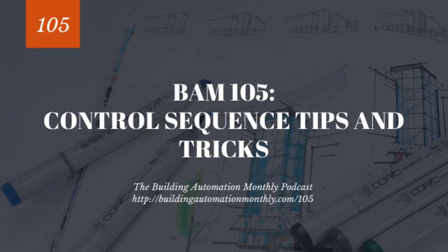And so we, and I'm not proud of this, but we troubleshot that thing to death. I mean, if it was a horse, we beat it to death, brought it back to life, beat it to death, and brought it back to life again. I mean, we checked PID loops, set points, everything. But what we didn't check was the balancing valve on the pump. And it's embarrassing, too, because I know that we'd probably walked by that pump several times, and I know that we probably had heard it, and we're thinking, that pump doesn't sound right. But we were so focused that we didn't think to go, that pump doesn't sound right. Until one day we did.